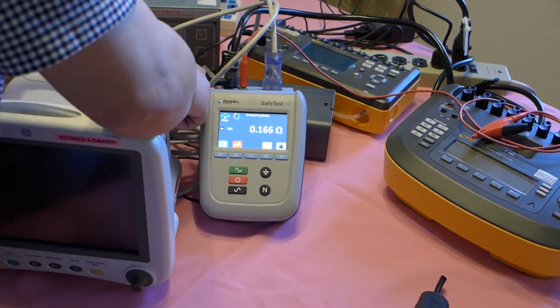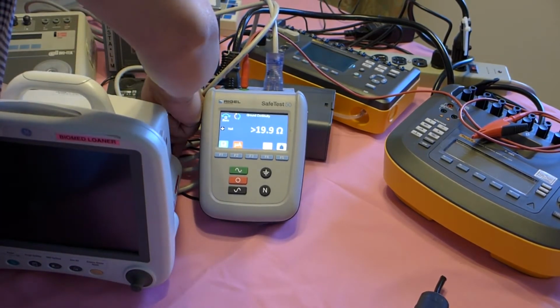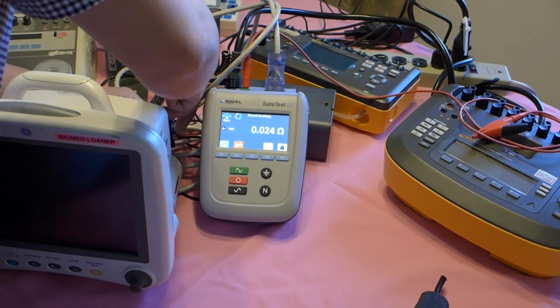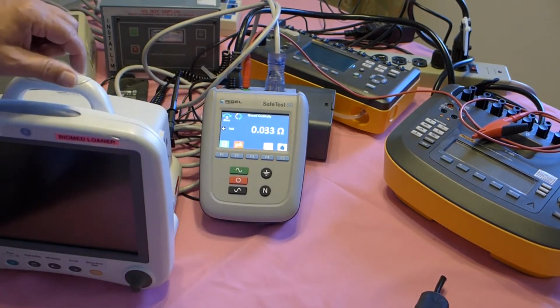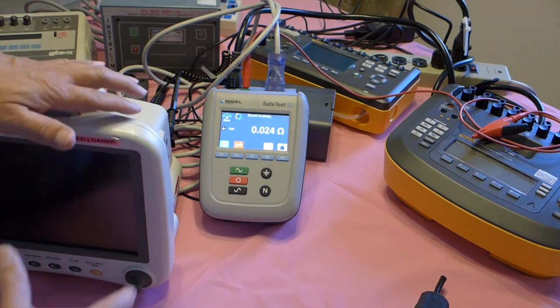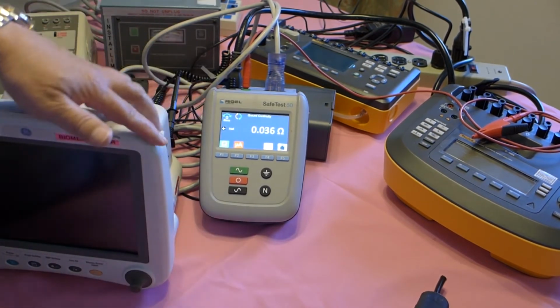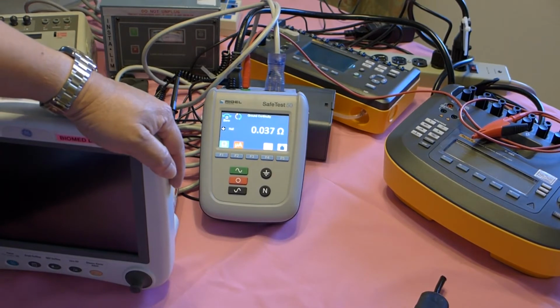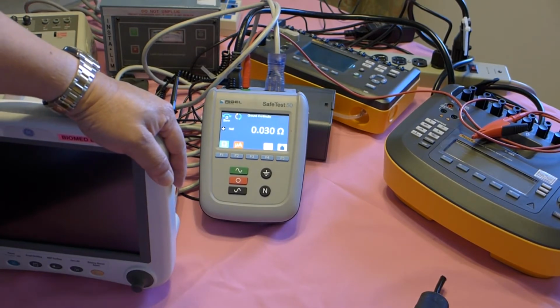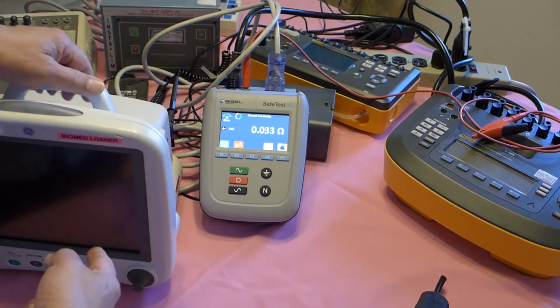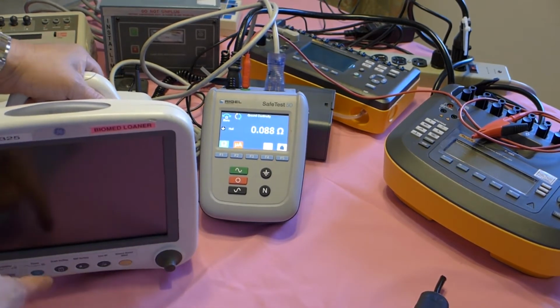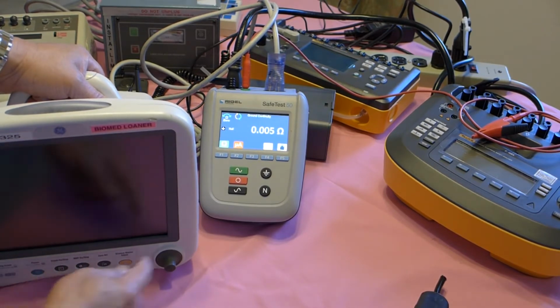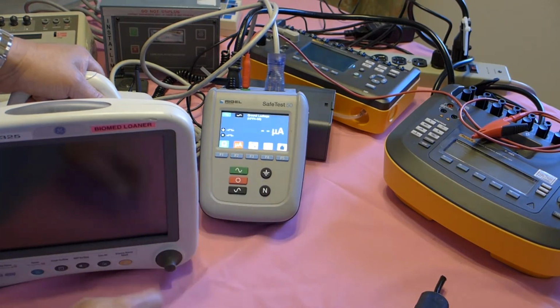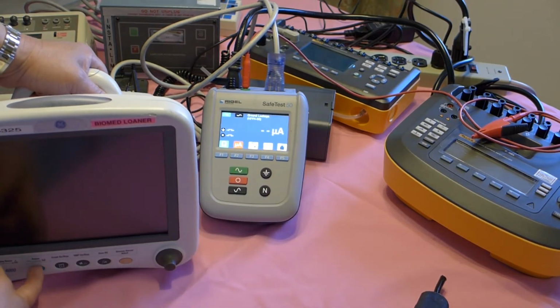The other thing we want to do is check leakage current. Leakage current only occurs when the device is plugged into the receptacle on AC power, and we have to turn the monitor on. So you need to make sure you turn on the leakage function and turn the monitor on.